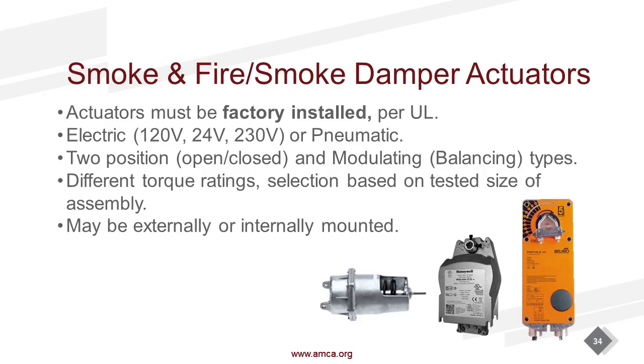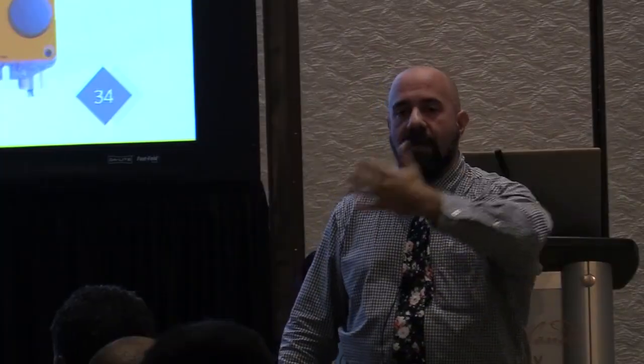So for my specifiers in the audience, don't go into your written specs and say every actuator is to be actuator model XYZ. Damper manufacturer A tests with actuator A. Damper manufacturer B tests with actuator B, C, and so on and so forth. We all choose, based on our own R&D and our own products, what we want to test and rate. No two listings are identical for any damper manufacturer. We have shared and common listings, but each model is tested and certified independently. So for my specifiers and my installers, if you're used to manufacturer A and that's all you know, and you have to use another manufacturer, do your research. Don't assume everything is the same.